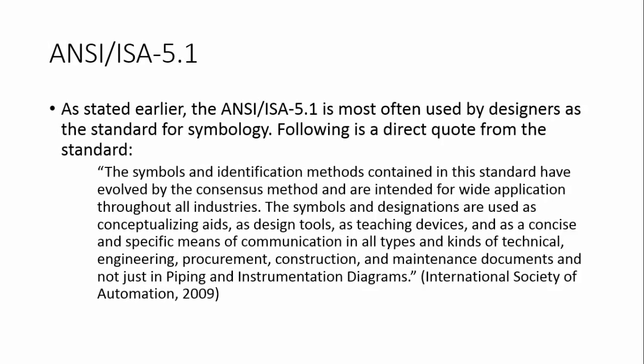So, as I stated earlier, the ANSI ISA 5.1 is most often used by designers as a standard for symbology. Even though it's not a standard by law, most people follow that standard. And here's a direct quote from that standard. The symbols and identification methods contained in this standard have evolved by the consensus method and are intended for wide application throughout all industries. The symbols and designations are used as conceptualizing aids, as design tools, as teaching devices, and as a concise and specific means of communication in all types and kinds of technical engineering, procurement, construction, and maintenance documents, and not just in piping and instrumentation diagrams.